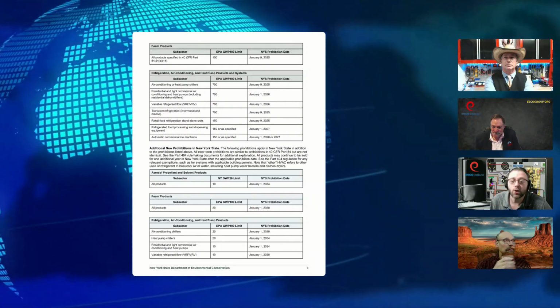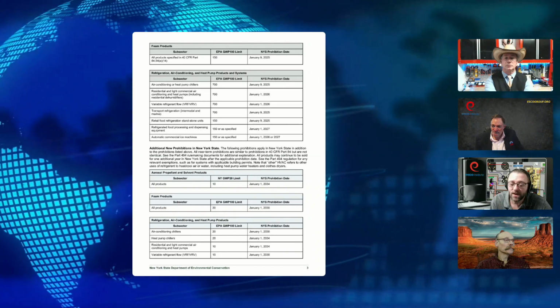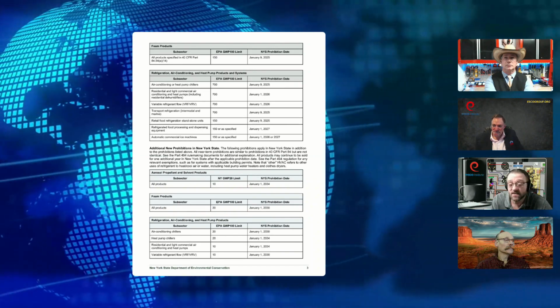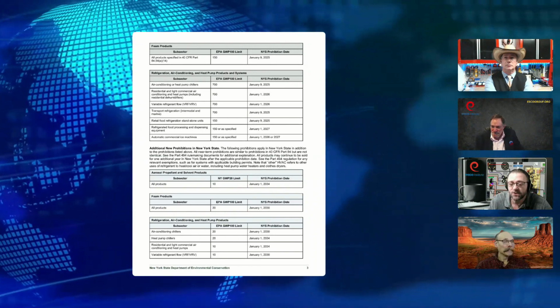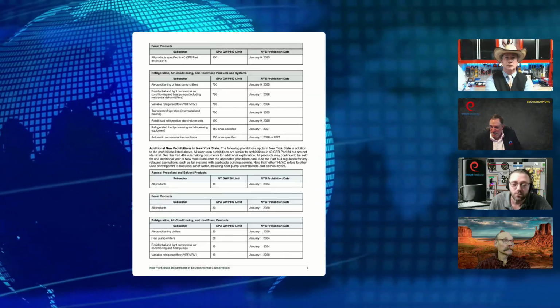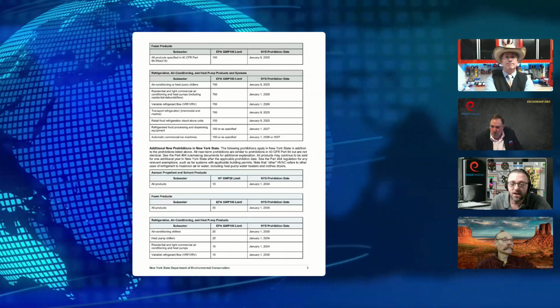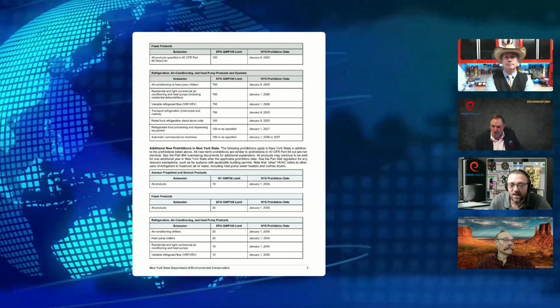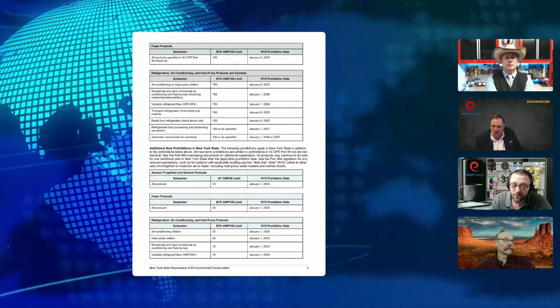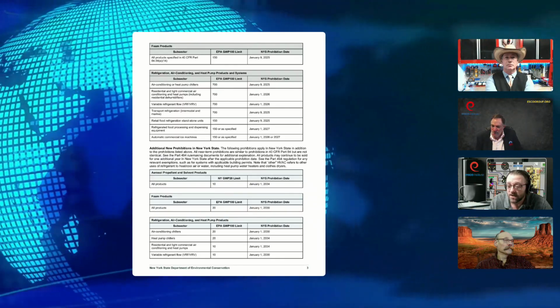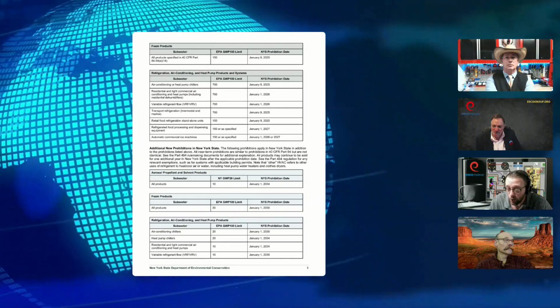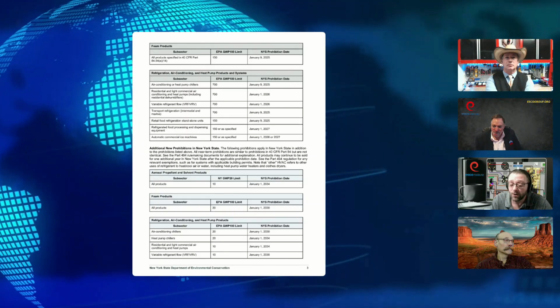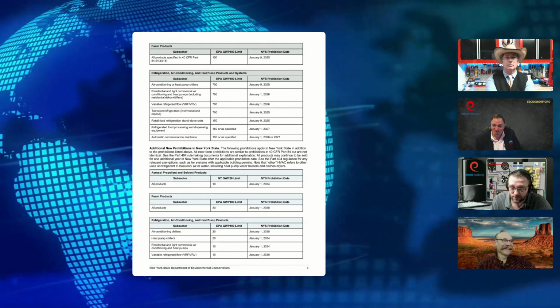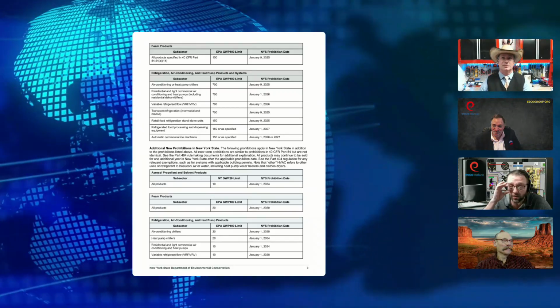Let's say we chose propane. Propane has to be EPA SNAP approved for every application it's used in. If we chose something else, it would also have to be EPA SNAP approved for that application. So you need UL standards, ASHRAE standards, EPA SNAP approval, and then you have to update building codes to allow and adopt all these new standards. It's like a decade-long process.